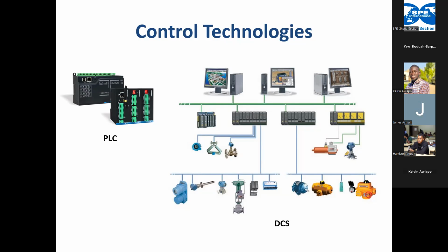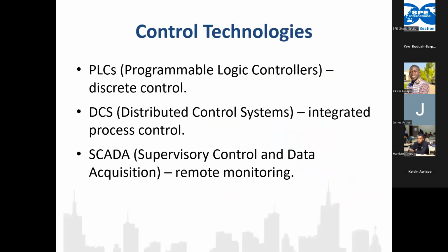And then we also have the SCADA system. Yes, supervisory control and data acquisition. It's similar to the DCS, but the major area of concern is monitoring. So for wide area monitoring, for instance, let's say monitoring the water network over a wide area, you need SCADA. The PLCs will be there in the field, giving you the data on the monitoring system. So you can be far away, and by the network, you'll be able to access and see whatever is happening at various areas.